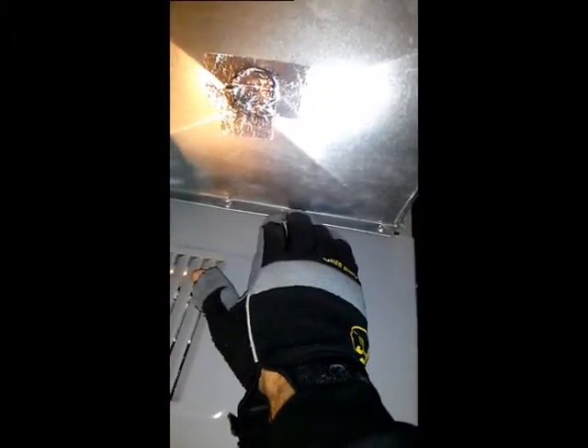So what I'm going to do to check the heat exchanger is go right through the plenum. There's no air conditioning in this furnace, which helps a lot. If there were air conditioning, the coil would be sitting up in the plenum, and it can make it more difficult to check this way, but I find this is the best way to check a heat exchanger because you get to actually look right down at it.